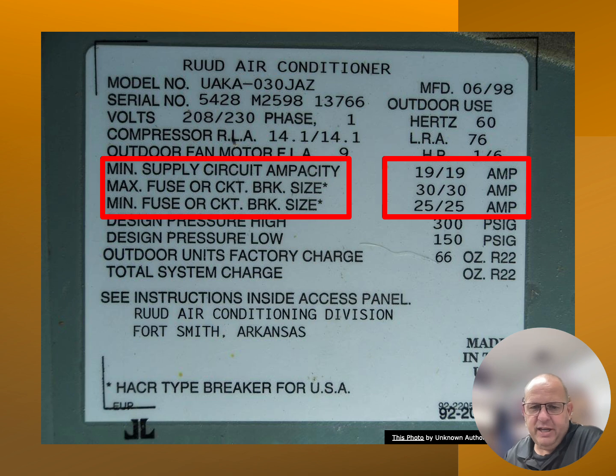Remember, 14 gauge wire is good for 15 amps, 12 gauge wire is good for 20 amps, 10 gauge wire is good for 30 amps. So if I put a 25 amp breaker, which is the minimum breaker I can install on this system, it's a common breaker in the field. What size wire can I use? Can I use a 12 gauge wire? The answer is no. NEC says nothing over 20 amps on a 12 gauge wire.